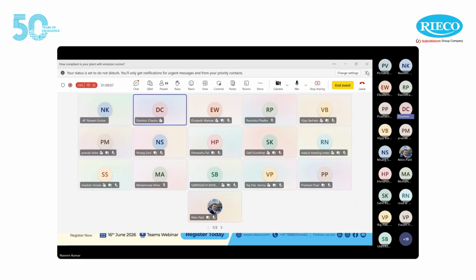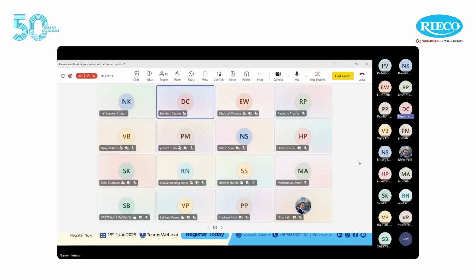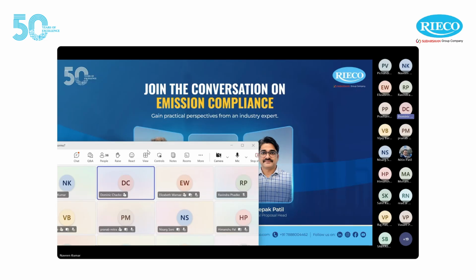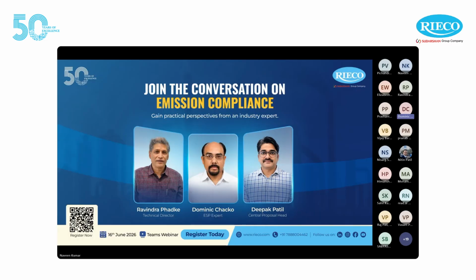Okay, when we talk about responsibility in operating electrostatic precipitators, I'm pretty sure that most of the plants have a few points in mind. And most obviously, something that starts with internal maintenance, maintenance of the ESP internals like collecting plates and discharge electrodes, rappers, and other auxiliaries. So I don't have to say anything very specific about that, except that you must ensure that your collecting plate and discharge electrode alignment should be perfect. The electrical clearance should be maintained. I think those sort of things are mostly known to everybody. But if there are any specific questions on that front, I can definitely address them.